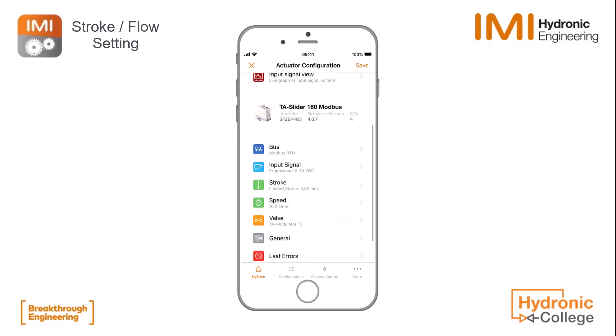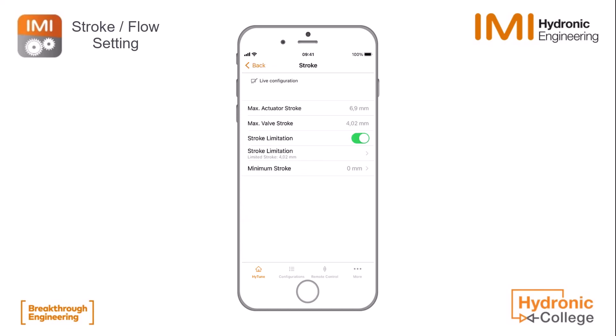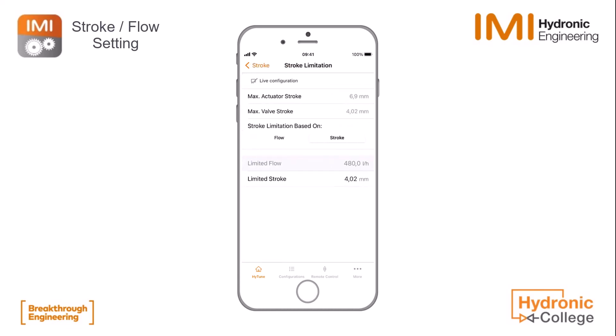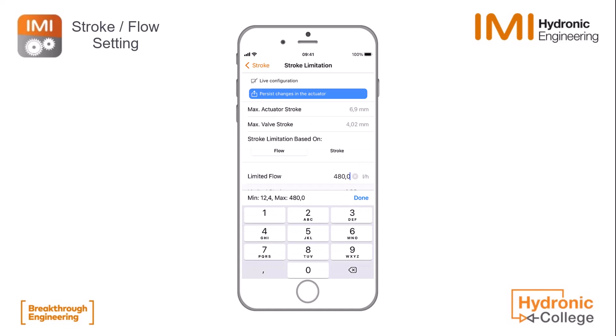Now we can set our stroke limitations. We go into Stroke and you see the limited stroke is at the moment 4.02 millimeters, and the stroke limitation is already on. The only thing we have to do is set the correct stroke limitation. We click on Stroke Limitation — the fourth option. You see that we are currently presetting on Stroke, but as we have set the correct valve, we can also limit on Flow, as Hytune knows which setting corresponds to which flow.